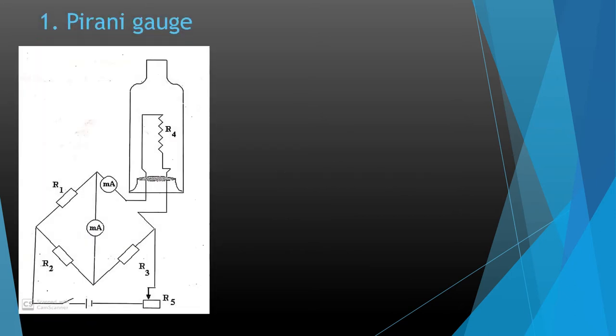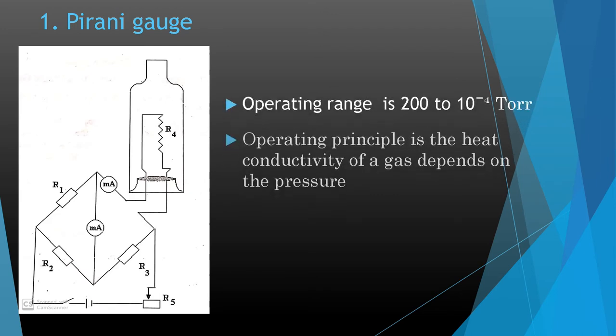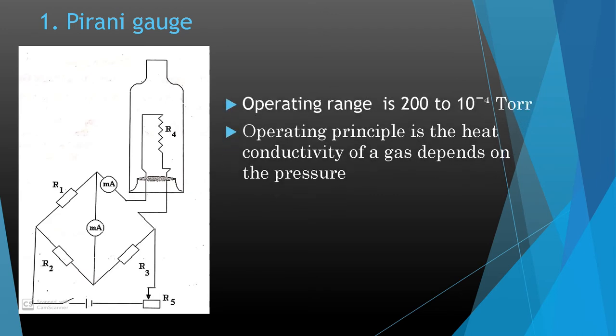Next is the Pirani gauge. This schematic diagram represents the Pirani gauge as an electrical circuit, which includes a Wheatstone bridge switch and a filament to be heated. The operating range is 200 to 10⁻⁴ Torr, and its operation is based on the fact that the heat conductivity of a gas depends on its pressure.